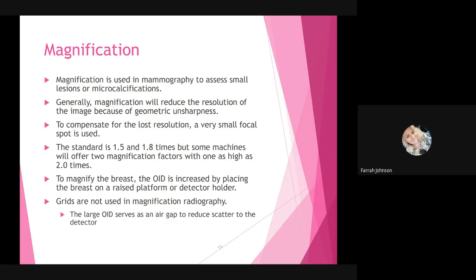So magnification, we use this all the time in mammography, and it's used to assess small lesions or microcalcifications. Generally, magnification will reduce the resolution of the image because of geometric unsharpness. So to compensate for the lost resolution, a very small focal spot is used. Now, the standard is going to be 1.5 and 1.8 times, but some machines will offer two magnification factors with one as high as 2 times.